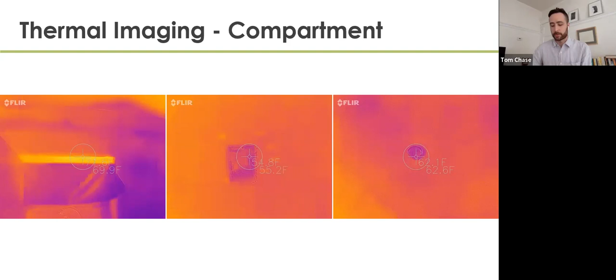We also do duct testing—the central ventilation system duct testing that Michelle was talking about before. For PHIUS in particular, that testing could be owned by the rater verifier or by an independent testing entity, which can be a sub to the HVAC contractor. There's also in-unit duct tightness testing, which is a passive house requirement and an Energy Star requirement, with a slightly different standard.